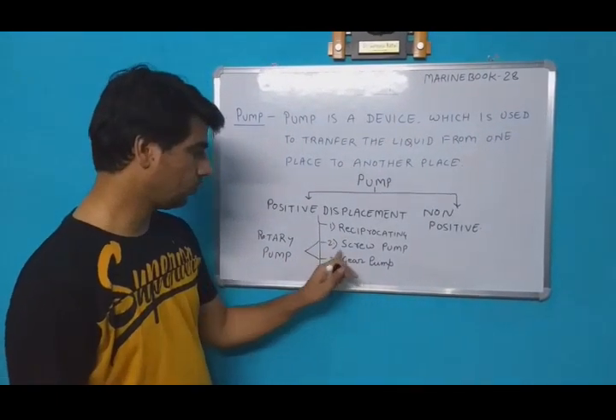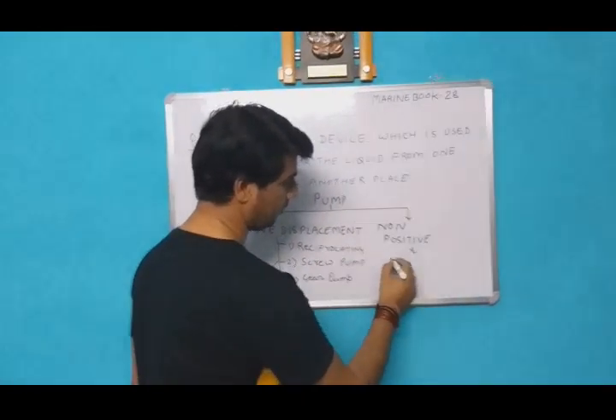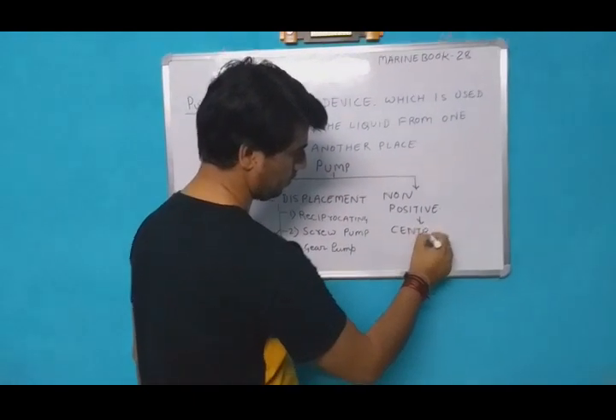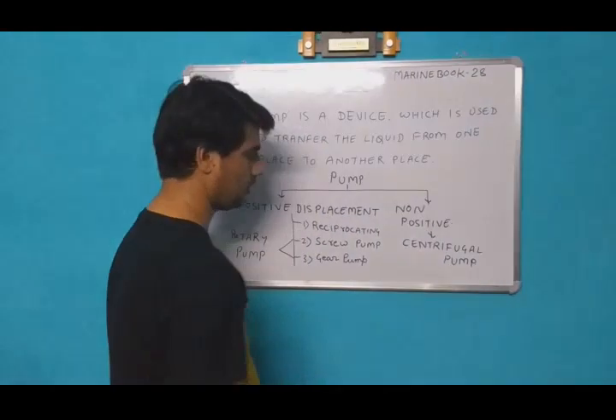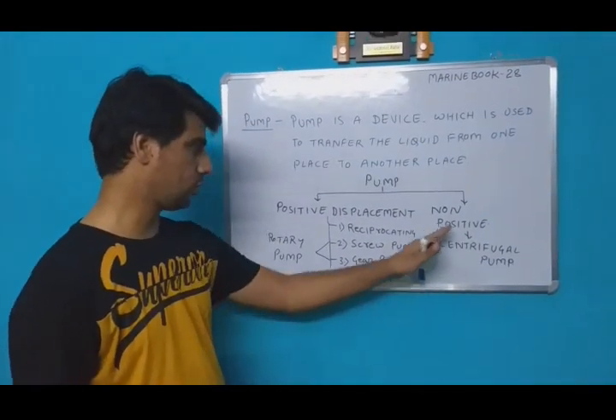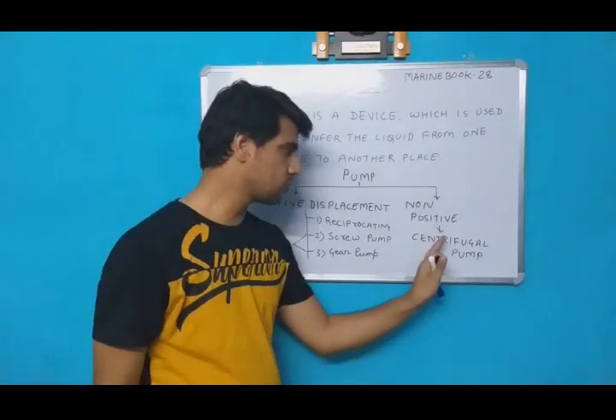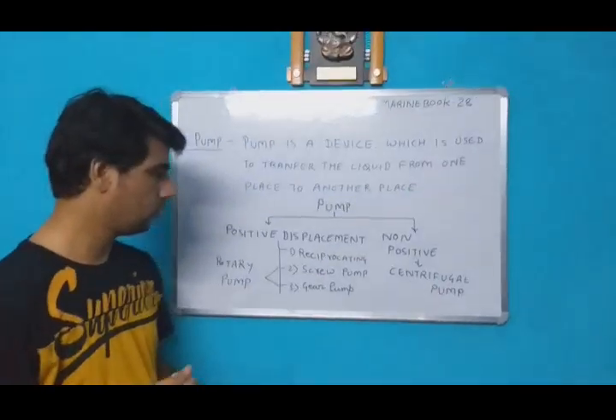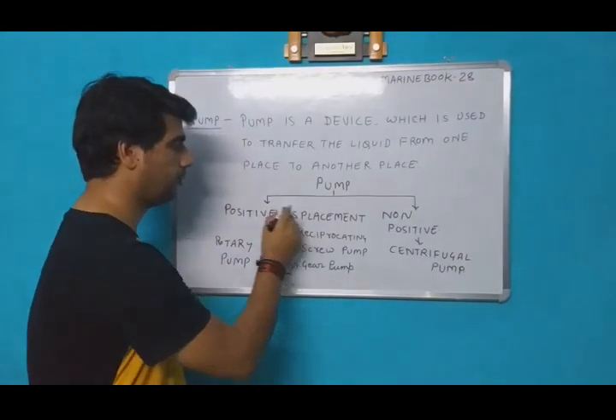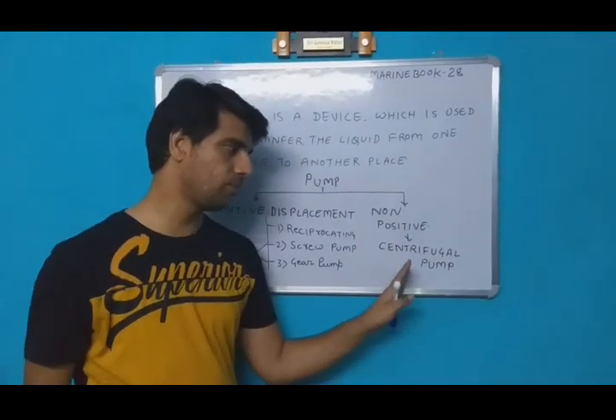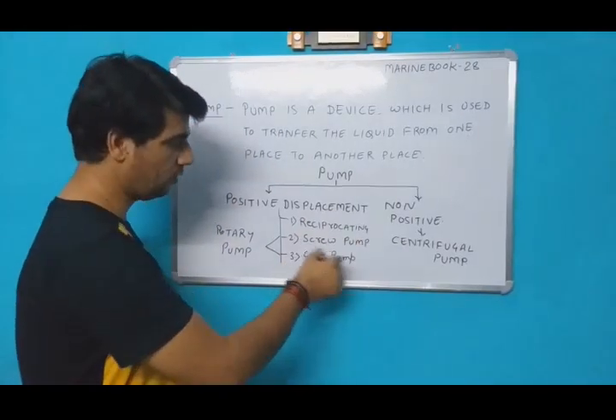Rotary pump is divided into two categories: screw pump and gear pump. Now the non-positive displacement type pump is known as the centrifugal pump. What is the difference between centrifugal pump and positive displacement type pump? The positive displacement type pump does not require priming, but the non-positive displacement type pump always requires priming. So the reciprocating pump, screw pump, and gear pump work as priming pumps, whereas the centrifugal pump requires priming but does not work as a priming pump.